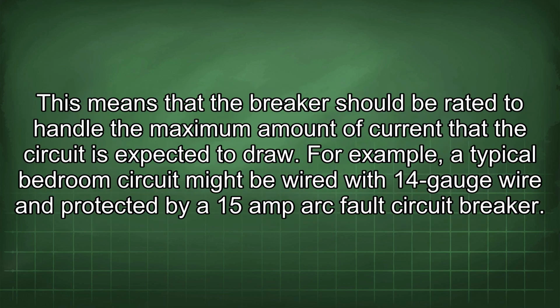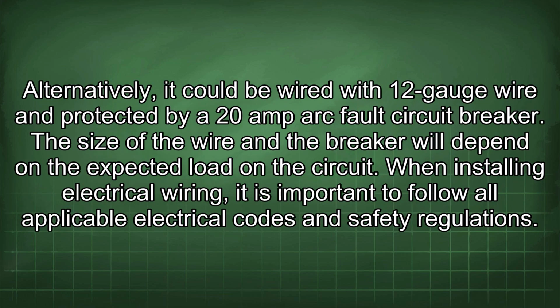This means that the breaker should be rated to handle the maximum amount of current that the circuit is expected to draw. For example, a typical bedroom circuit might be wired with 14-gauge wire and protected by a 15-amp arc fault circuit breaker. Alternatively, it could be wired with 12-gauge wire and protected by a 20-amp arc fault circuit breaker. The size of the wire and the breaker will depend on the expected load on the circuit.